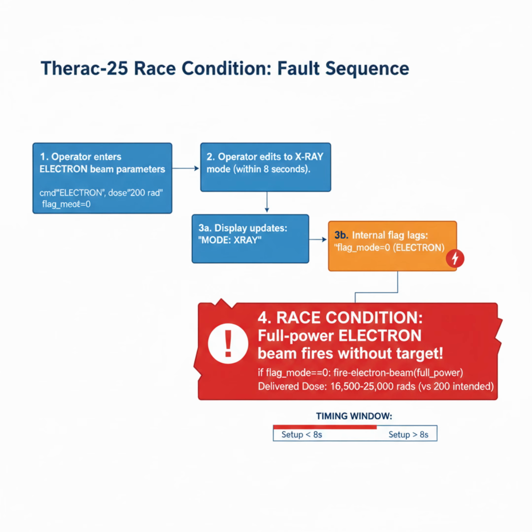Here's the sequence. An operator would enter data for one mode, say electron beam therapy, then realizing they needed X-ray mode instead, they would quickly cursor back up and change the mode selection. If this happened within about 8 seconds, before the turntable had time to complete its rotation, the software would sometimes get confused. The display would show X-ray mode. The operator would believe the machine was configured correctly, but internally a flag controlling the turntable position hadn't updated. The software thought the machine was still in electron mode.